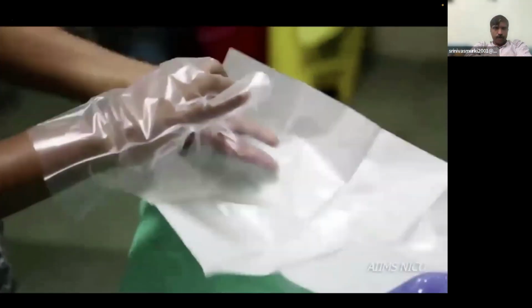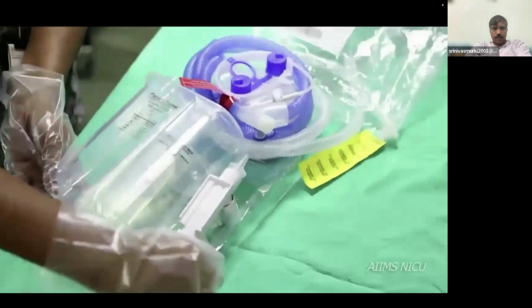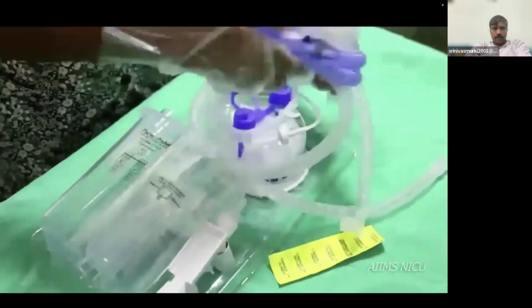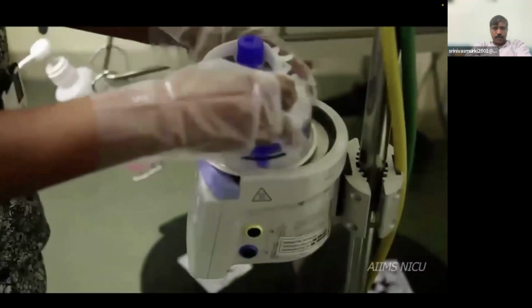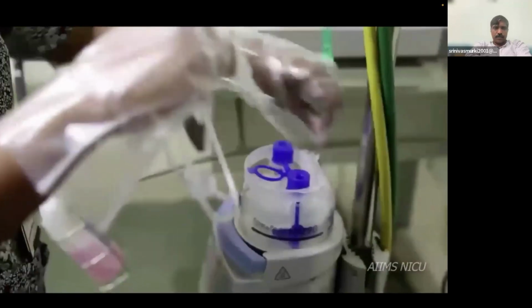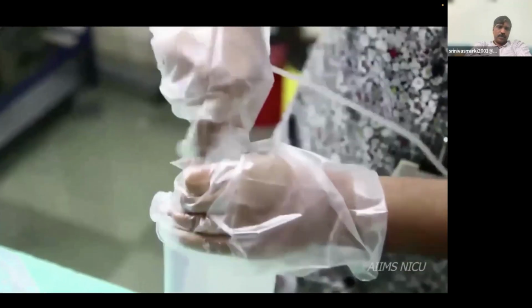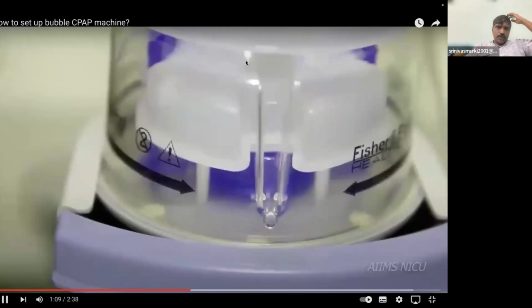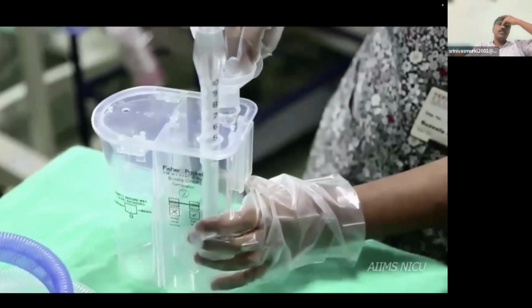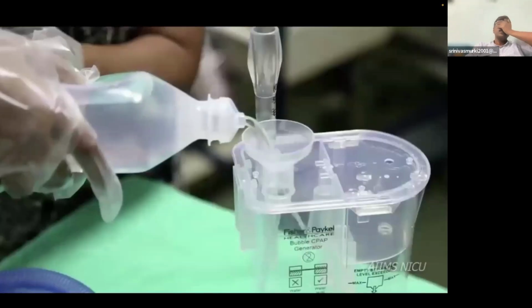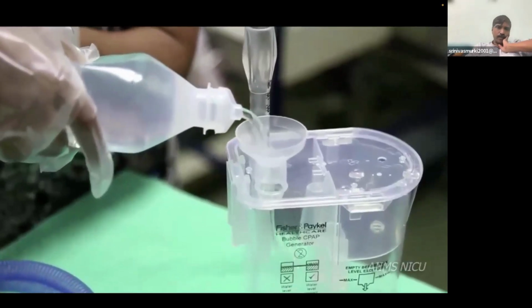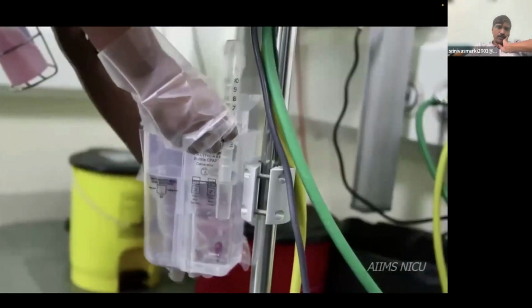and wearing clean gloves, open the disposable CPAP circuit. Fix the water chamber onto the servo humidifier and fill it with distilled water. Use the autofill option of fixing the distilled water bottle to a stand for filling the water chamber.